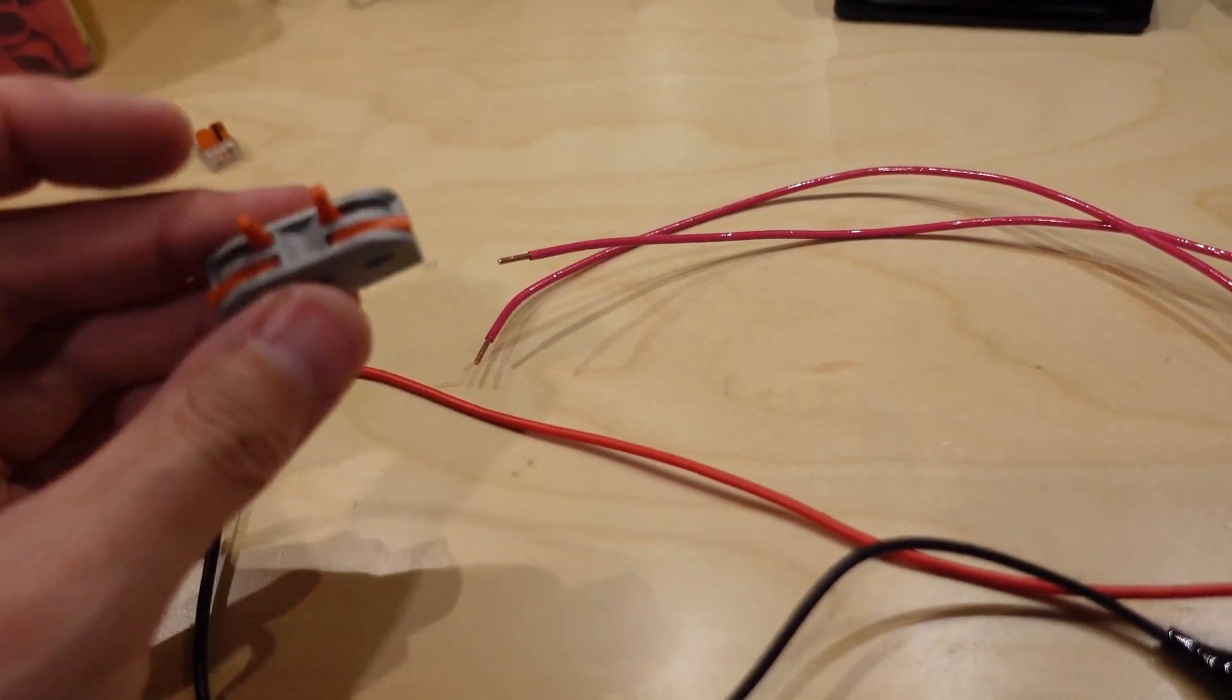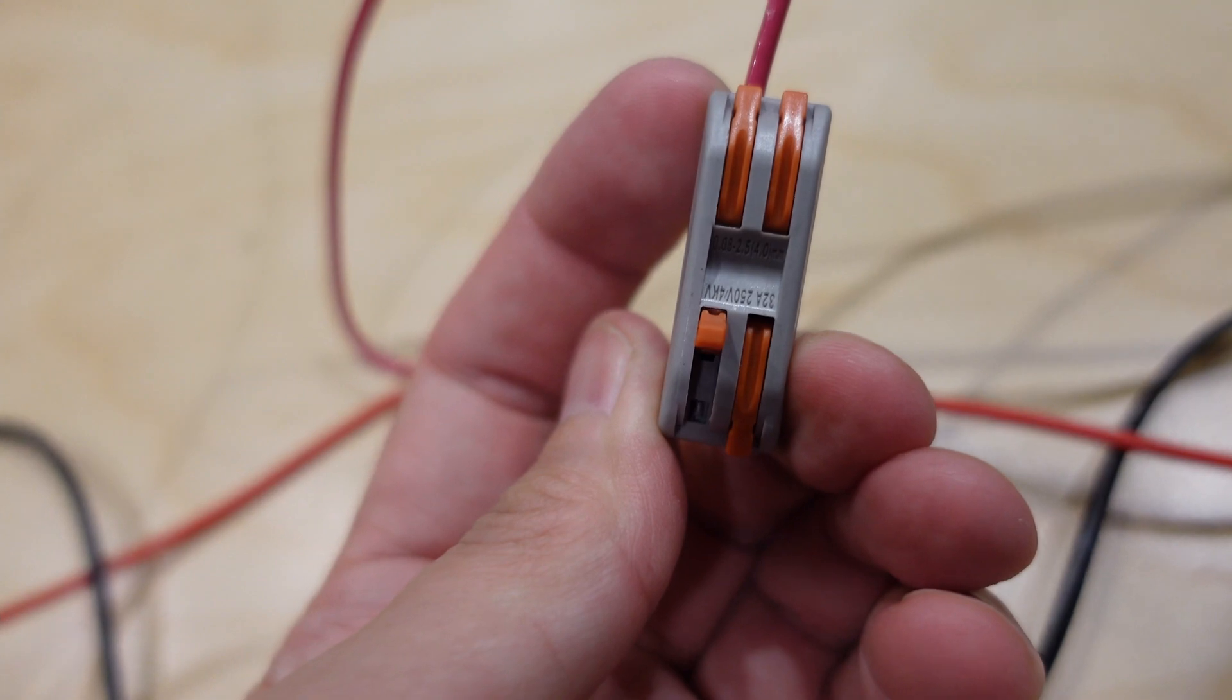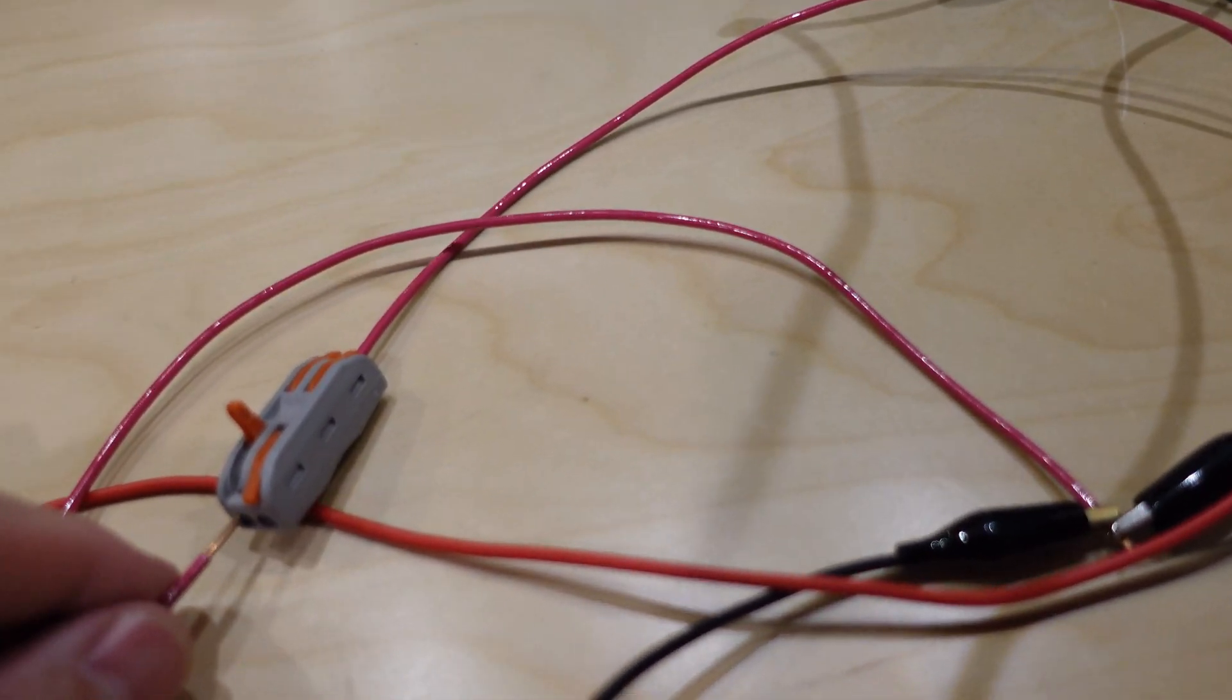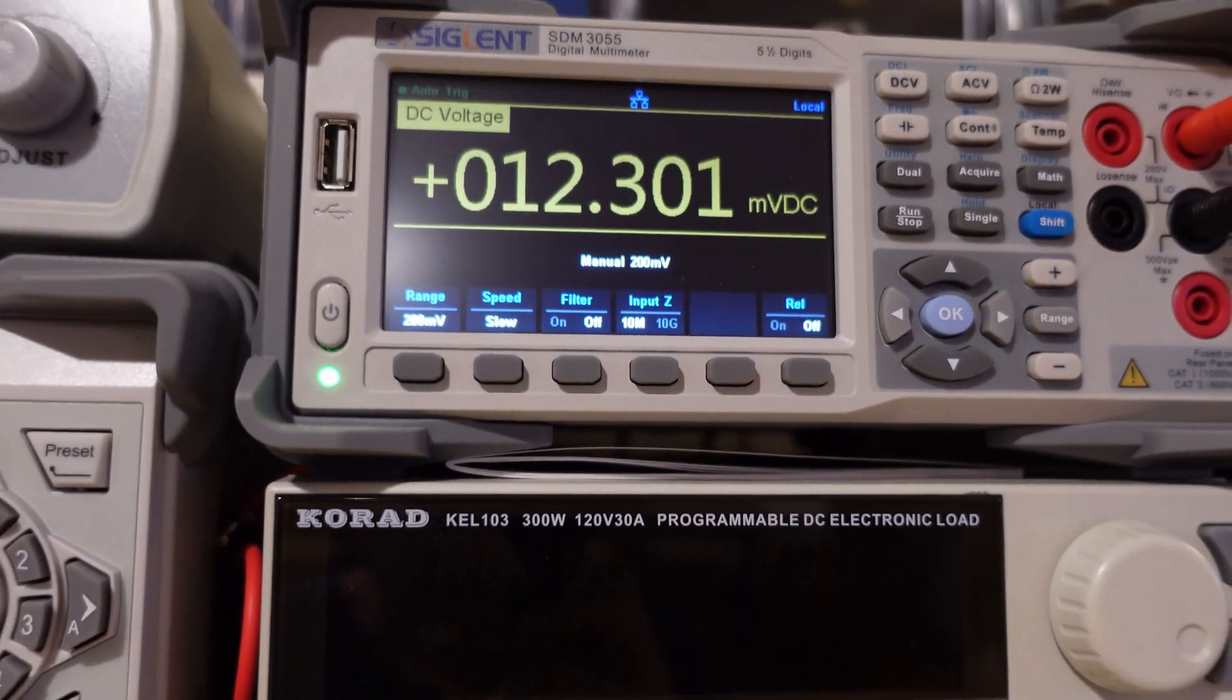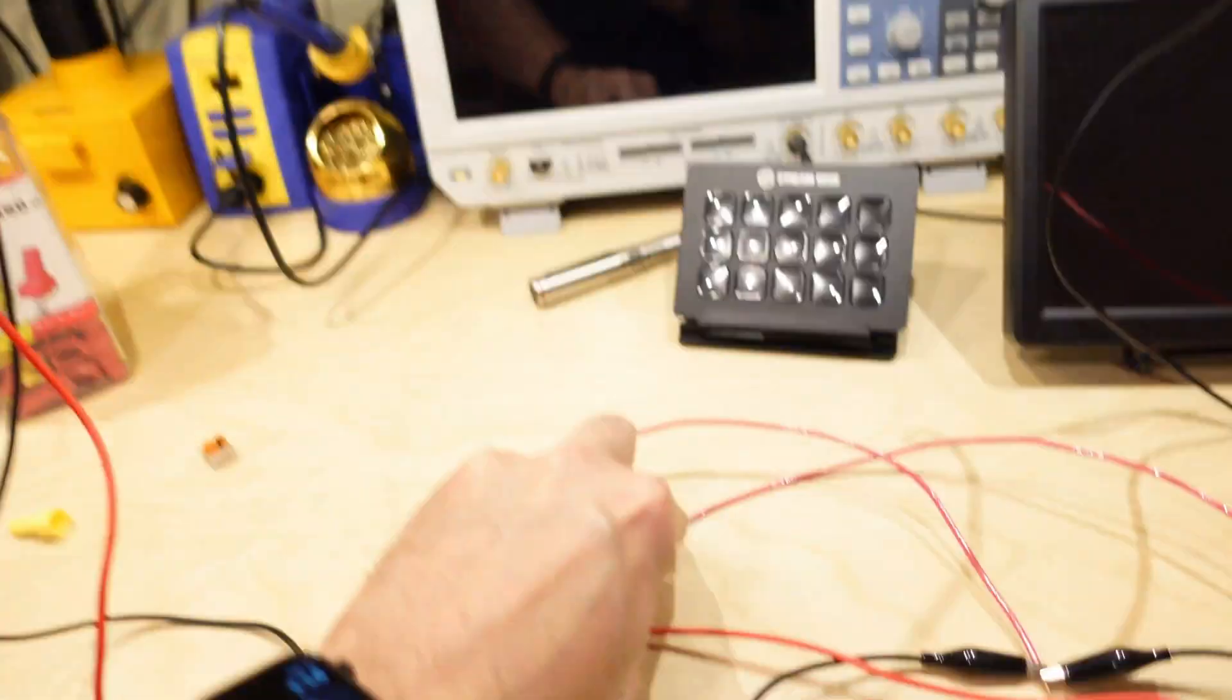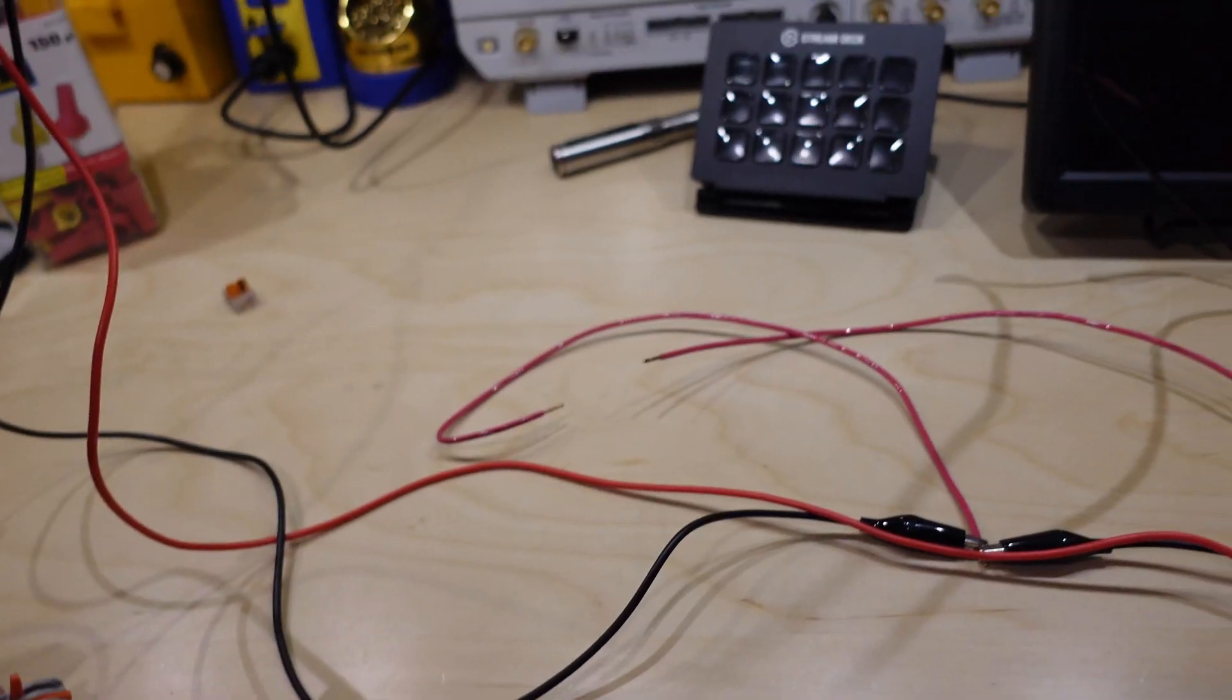Just for comparison, this is a cheap lever splice that I got from Amazon. 32 amps, 250 volts. Yeah, right. No way. I only use these for low voltage applications. So let's stick that wire in there. Clamp the clamp down and see what we've got. So this started out lower. It's going up. There we go. If I physically manipulate it a little bit, just kind of pushing on it with my hand, which is probably not fair because I wasn't pushing on the WAGO. So if I let go of that, we're up to 20. Significantly poor performance compared to the WAGO, which is kind of what you would expect.